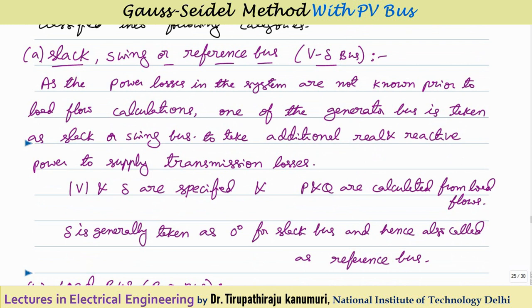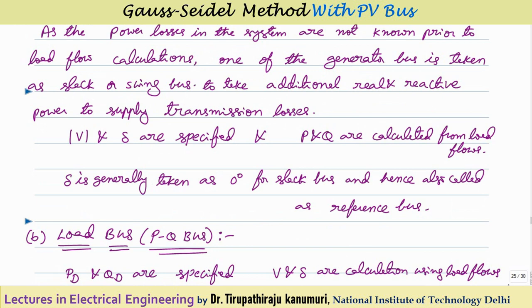Based on which quantities are specified, buses are broadly classified into the following categories. The first is called the slack bus, swing bus, or reference bus. One bus is taken as the slack or reference bus for making all calculations. The main reason is that power losses in the system are not known prior to load flow calculations, so one generator bus is taken as slack to supply the additional real and reactive power for transmission losses. For the slack bus, voltage magnitude and delta (taken as zero) are specified; P and Q can be any values.